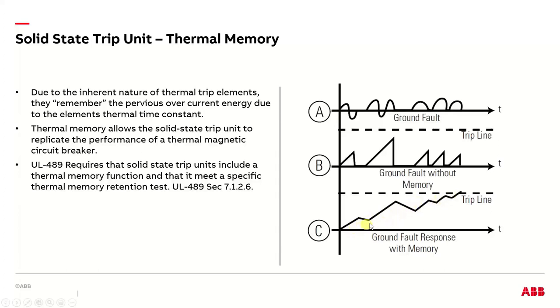So it's giving you a true protection of what is actually happening at the load thermally. That's a big improvement that is actually just being enforced now in the new UL489 standard. The standard requires a thermal memory with a retention test in order for a breaker to have that UL listing. And frankly, we had our Spectra line of breakers, and our standard Spectra, which was electronic trip, true RMS, didn't have a memory. So we're bringing that breaker into obsolescence because this was one of the drivers, because we would have had to do a major redesign to bring that breaker up to the new UL listing, which I think is coming into effect next year or the year after.